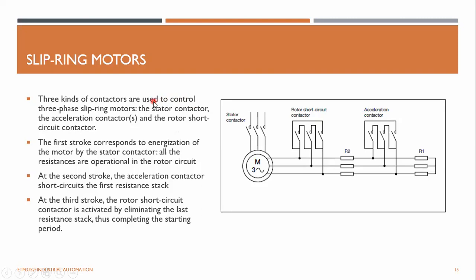Now, as you know, there are some motors called slip ring motors. The rotor also has some winding, so you can use this winding for speed control. Right. So three kinds of contactors are used to control three-phase slip ring motors. Start contactor, stator contactor. This is the stator contactor. So you don't need to worry about the motor winding from outside. You just connect it to the main supply. This is the rotor. So the rotor also has wiring. So you take the rotor winding outside.